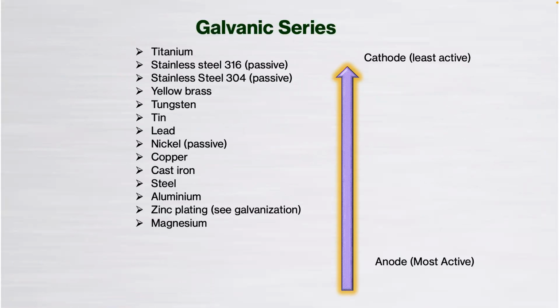The reason I'm showing you this is there's something called galvanic corrosion you may or may not have heard of. It's very unlikely that we find nowadays systems that have all the same metals throughout the system. A lot of old installations going back many years, and even I was working with a client who's got a system that's 100 years old, believe it or not, or the pipework is at least, and everything is mild steel. But very rarely you're going to find systems now that don't have mixed metals throughout the system. So the further apart on the galvanic series these metals are, the more reactive they're going to be. And one is going to act as the cathode, or it's least active, and the anode is the most active. And then we're going to see a rapid level of corrosion.